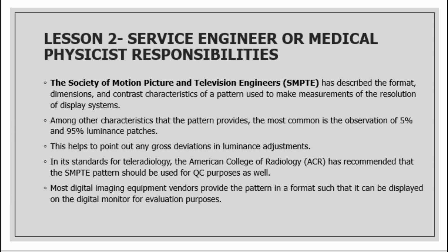teleradiology. Later on, we will discuss what is your teleradiology. Okay, so it is a standard for teleradiology. The American College of Radiology or your ACR has recommended that the SMPTE pattern should be used for QC purposes as well. Okay, so most digital imaging equipment vendors provide the pattern in a format such that it can be displayed on a digital monitor for evaluation purposes. Okay, so this is your SMPTE.